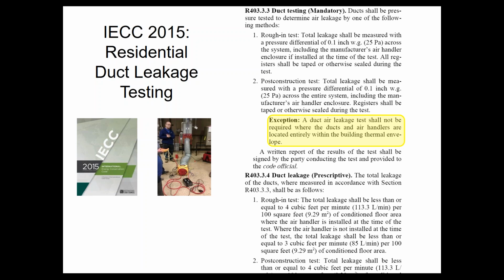Bronson types in a question: is the AeroSeal report accepted by code for leakage testing? The leakage test report would be going to your local code official. I am not aware of any local code officials that are not accepting that report. Some of them may, some of them may not. The code book itself does not specify what the report needs to look like. Some municipalities I know for sure, like Naperville, which is in the town next to me, accept the AeroSeal report. One of the residential dealers spent time with them 3-4 years ago, showing them how the system worked and how the reports looked and everything.